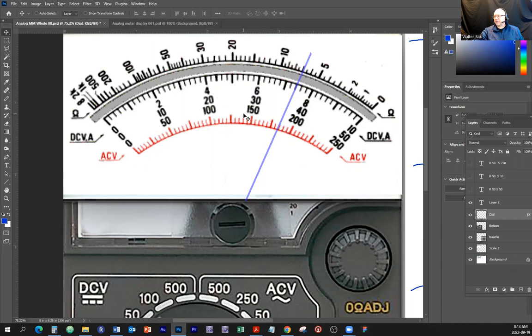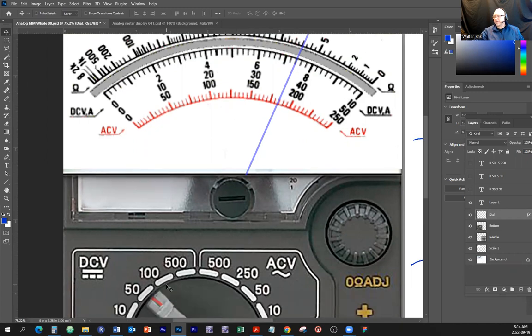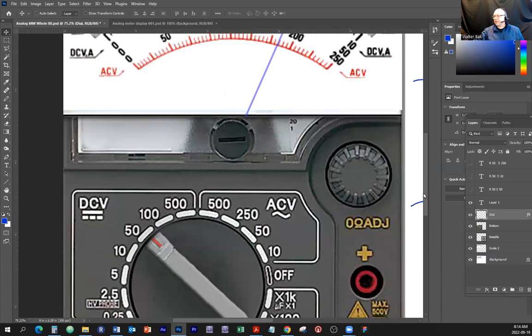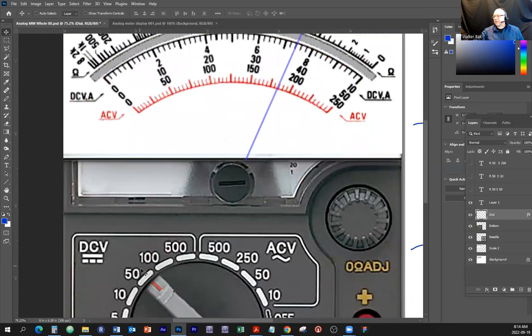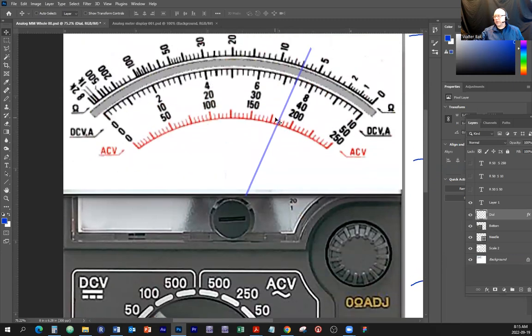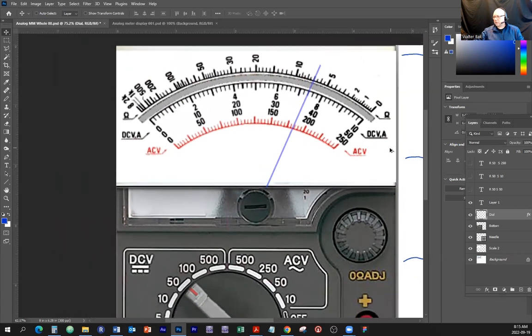But what if we don't have a scale that corresponds? Let's say there's a range of 100. We don't have 100 here. So now what I'm going to show you right now applies to pretty much all the measurements, you can just use that method and you'll be comfortable. So let's leave the needle as it is. Let's leave the range as it is. So on this scale, because it's 50 and this is 50, it's 1 to 1, so we're good. But what if we want to measure the same voltage, same swinging out of the needle, and let's say we get the same reading using a different scale? How do we use a different scale? We should get the same reading, right? Okay.